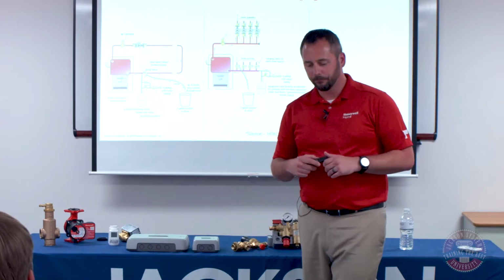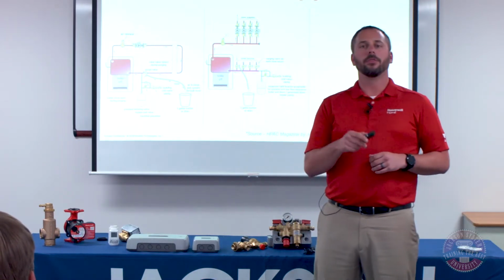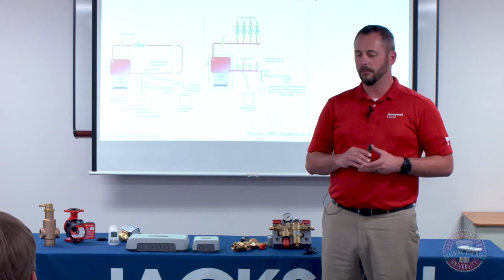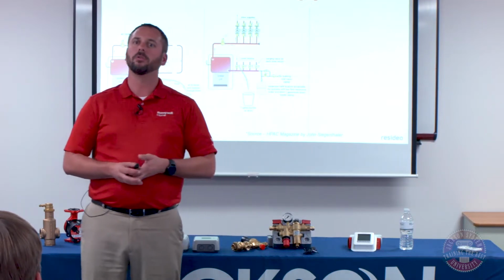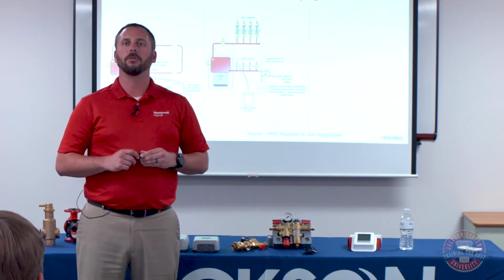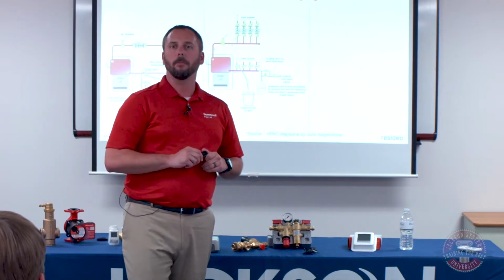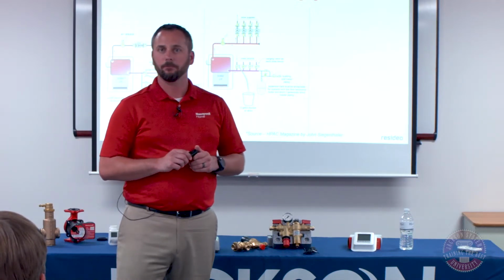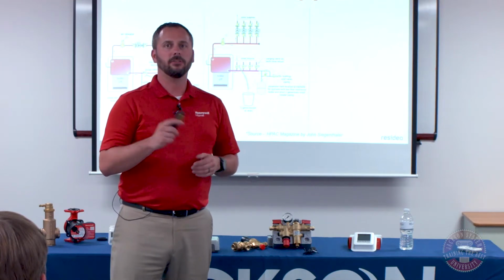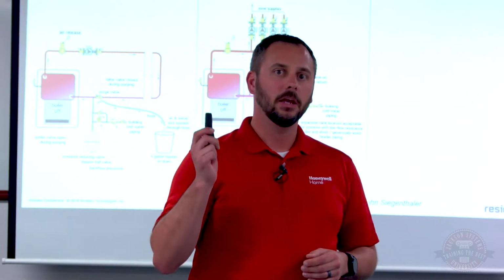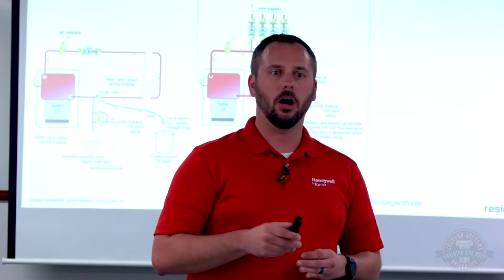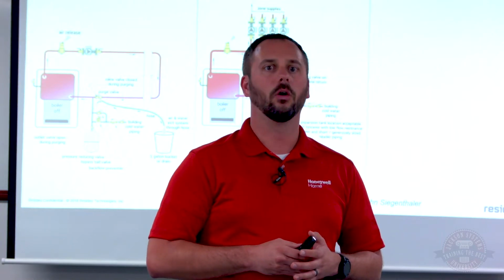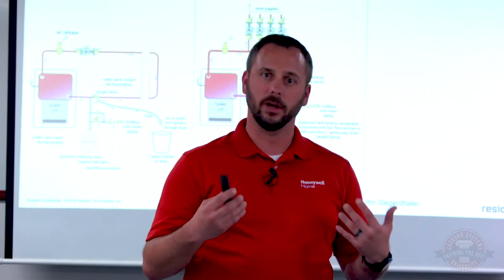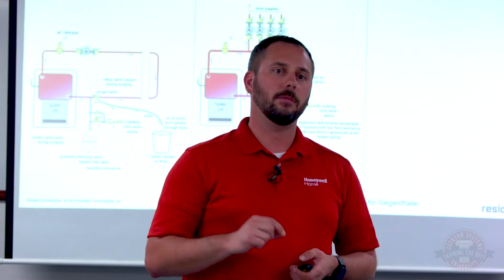But in this instance, we're bringing water up, we're going through the system, and we're going to have to go loop by loop. So what you're going to do is close off, in this example, the 3 zones on the right-hand side, and purge the first loop. Same type of setup. You've got a ball valve at the bottom with a boiler drain right above it, and you're purging through there. This is where I've seen a lot of people make the mistake and blame the PRV for not working properly. If you close that off while you're filling with city pressure, or say you're purging at 30 pounds, 50 pounds, whatever you're using, you're keeping 30 to 50 pounds in that loop.